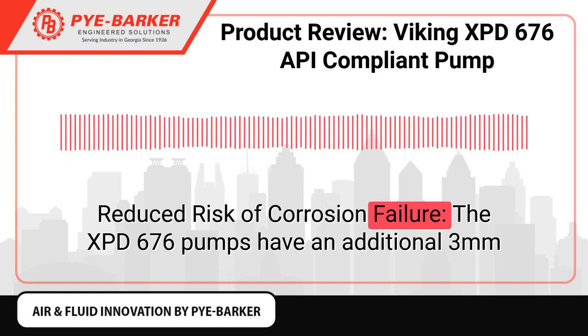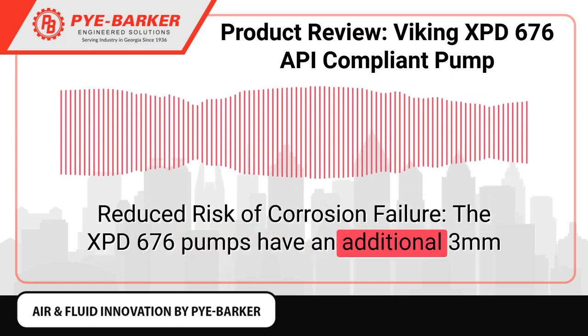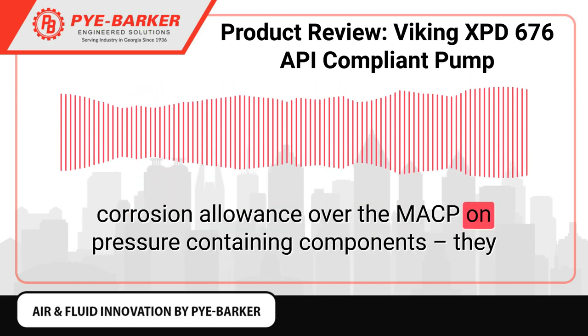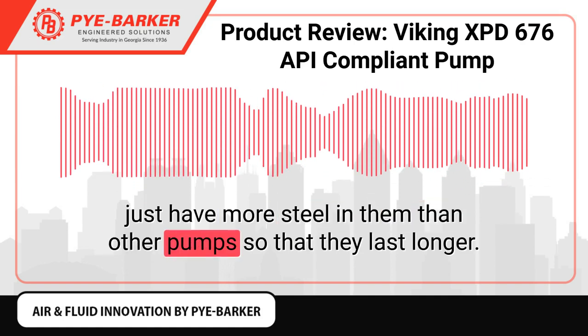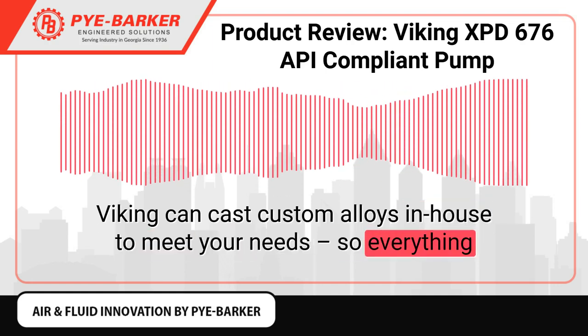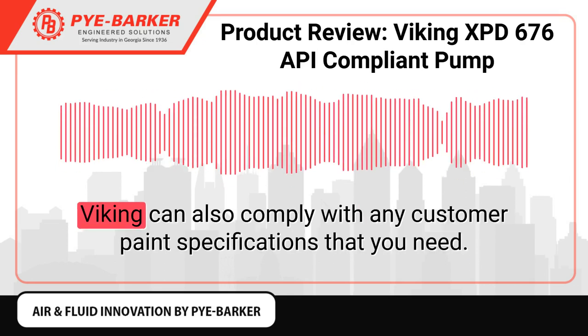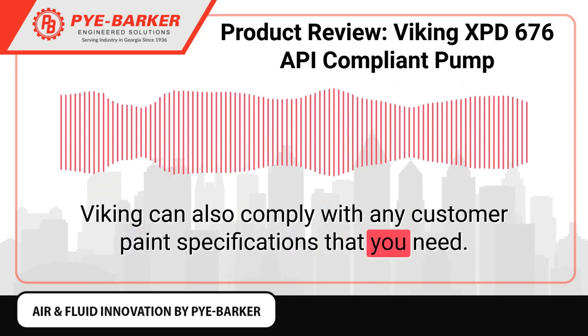Reduced risk of corrosion failure. The XPD 676 pumps have an additional 3mm corrosion allowance over the MACP on pressure-containing components — they simply have more steel in them than other pumps so that they last longer. Viking can cast custom alloys in-house to meet your needs, so everything remains above API 676 standard. Viking can also comply with any customer paint specifications that you need.